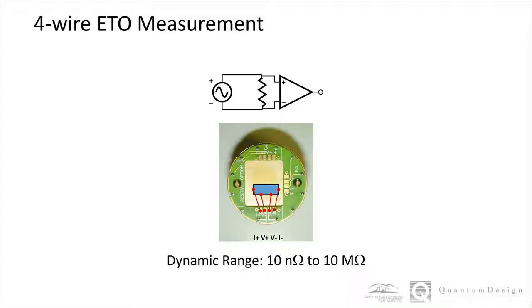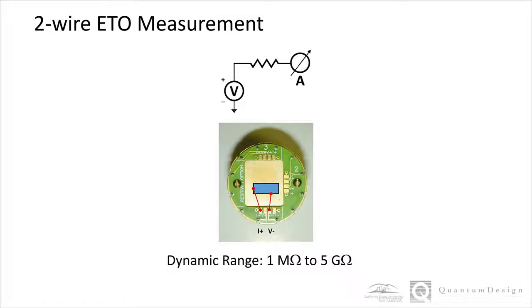The ETO can operate in a low-impedance 4-wire measurement mode or a high-impedance 2-wire measurement mode. In the 4-wire mode, the acceptable impedance range is between 10 nano-ohm and 10 mega-ohm. Two-wire measurements can be performed from 1 mega-ohm up to 5 giga-ohms.